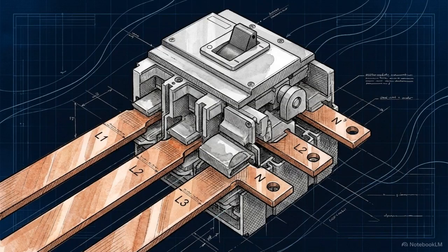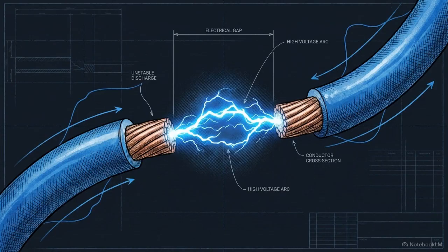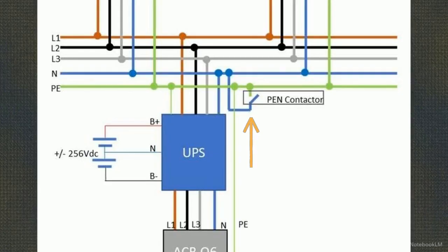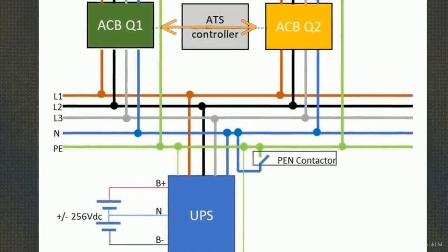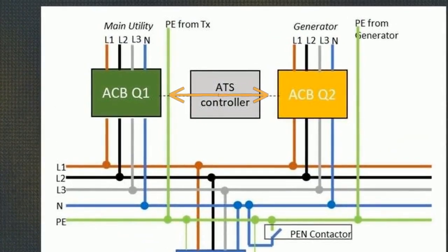Because Q1 and Q2 are 4-pole breakers, opening them severs the neutral connection to the facility. This leaves the UPS input neutral dangerously floating while both source paths are open. To fix this, at time T1, the system activates a transient PEN bonding connection. The PEN contactor energizes to temporarily bond the UPS input neutral to protective earth, maintaining a stable neutral reference while Q1 and Q2 are open.